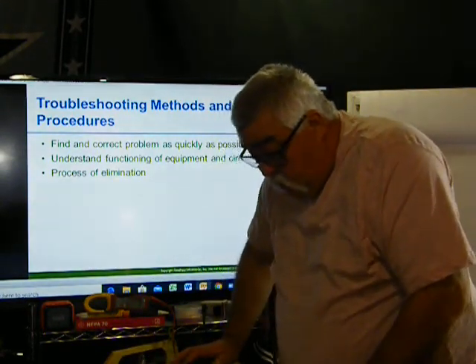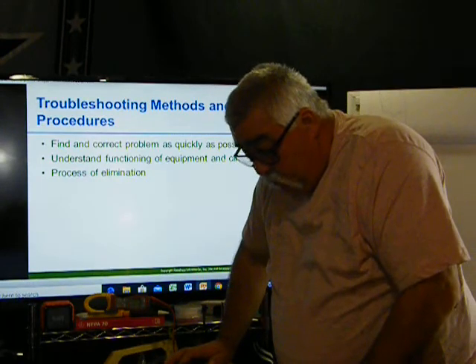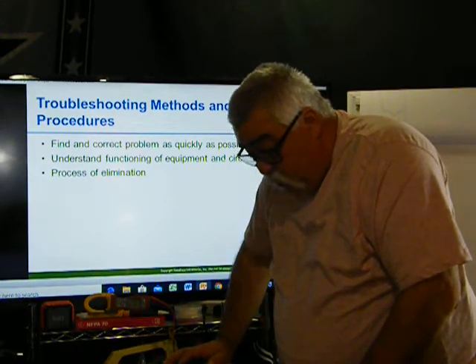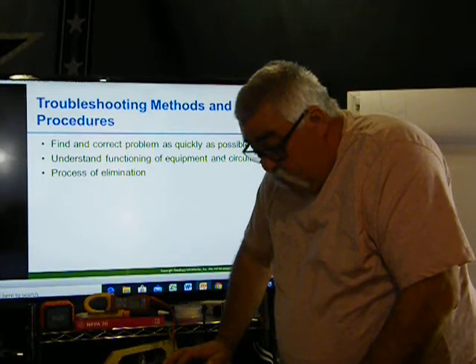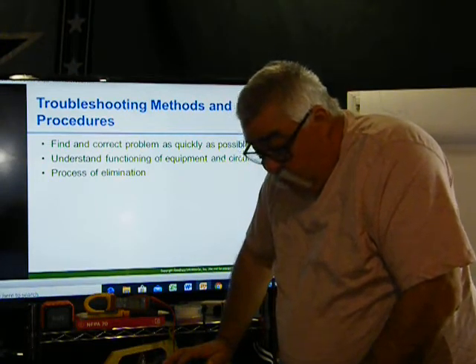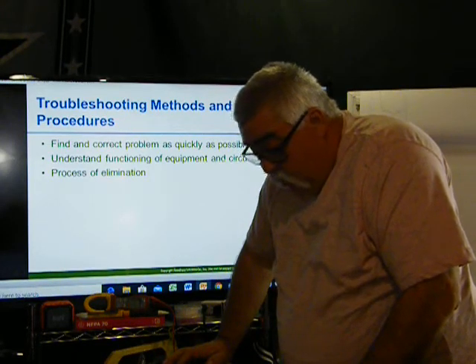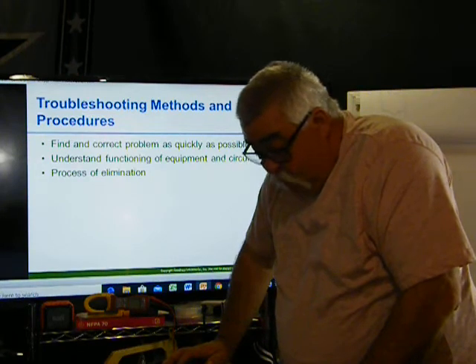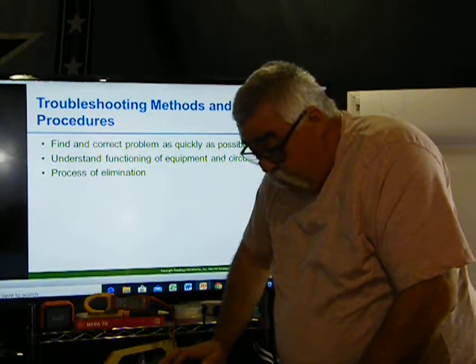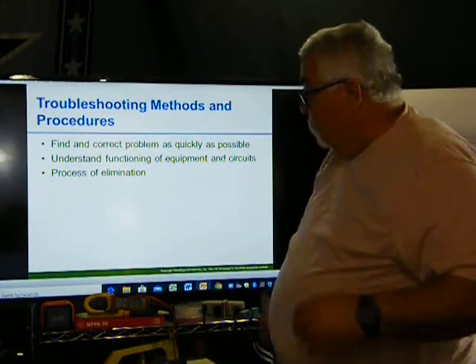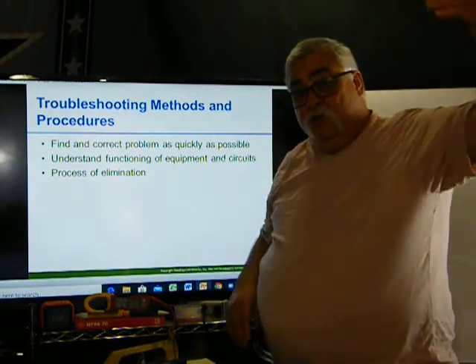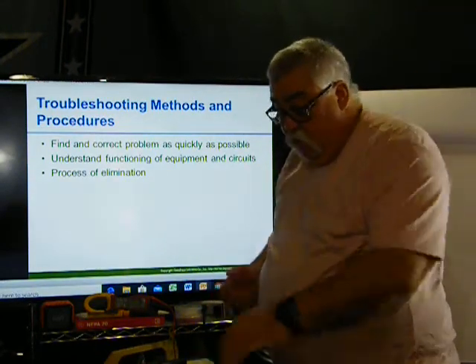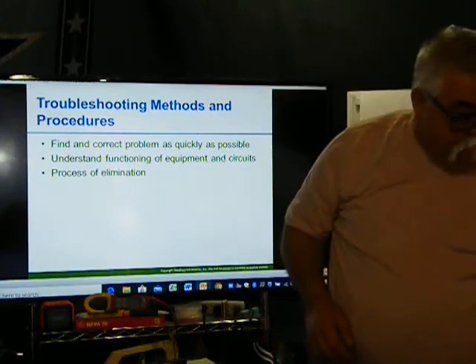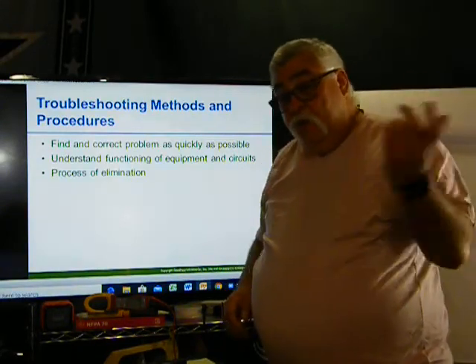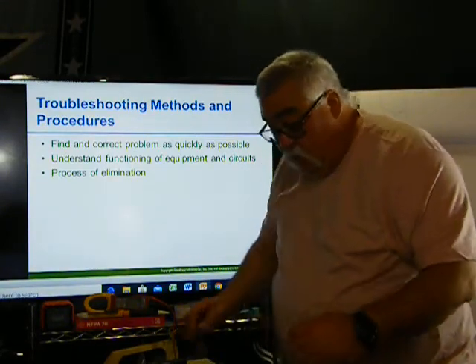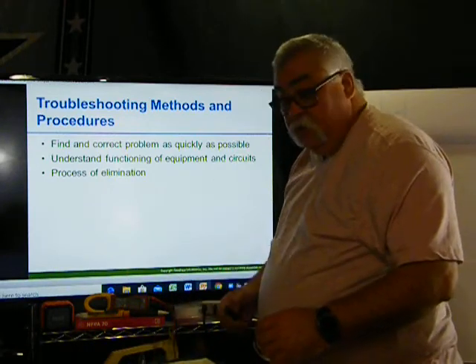It says, for example, power connection to the supply, circuit breaker, and fuse can be quickly checked. Check a distinct part of the equipment. Test the line side of the power circuit, then the load side, and move to the control circuitry. So you start the process of elimination. You start off at your supply. You can check it at the disconnect. Am I getting power from the disconnect? I'll go over to that. I hope the drawing's on there. I forgot to check.